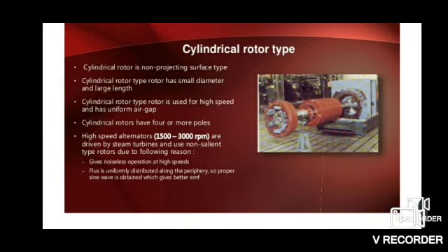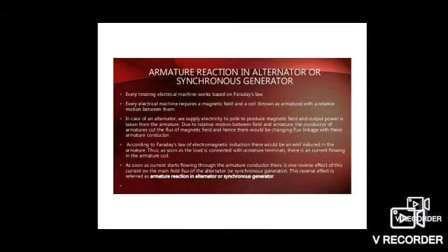High speed alternators, that is 1500 to 3000 rpm, are driven by steam turbines and use non-salient type rotors due to the following reasons. It gives noiseless operation at high speeds. Flux is uniformly distributed along the periphery, so a proper sine wave is obtained which gives better EMF. So cylindrical rotors are preferred in thermal power plants.